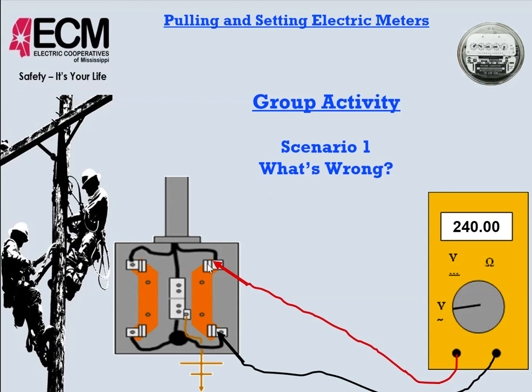So if we check from our line side to our load side like this on volts alternating current, and we get 240 volts, what would be the problem? Well, the problem here would be that both the line and the load side are energized and they're on opposite legs. So there'd be a potential difference of 240 volts between these two on the line and the load side. We know that there should be zero voltage on the bottom. There's probably still some power or some backfeed from somewhere, but definitely that's a meter that we could not set safely.